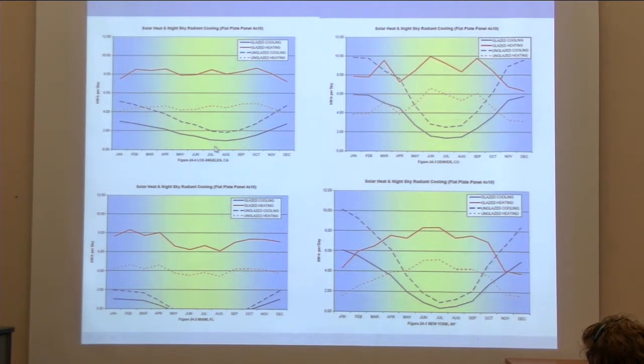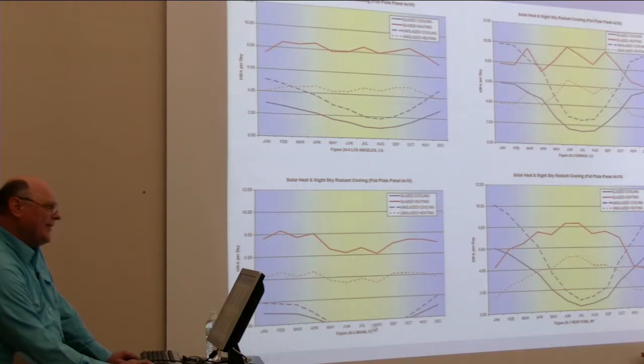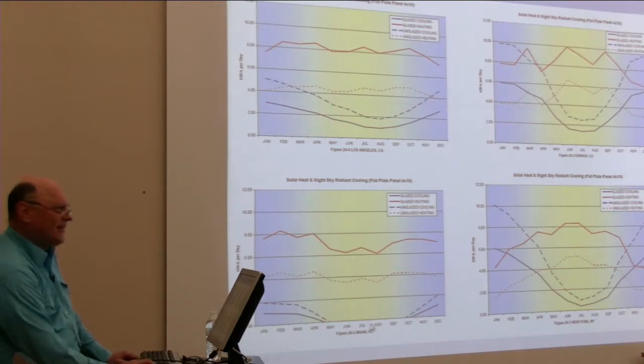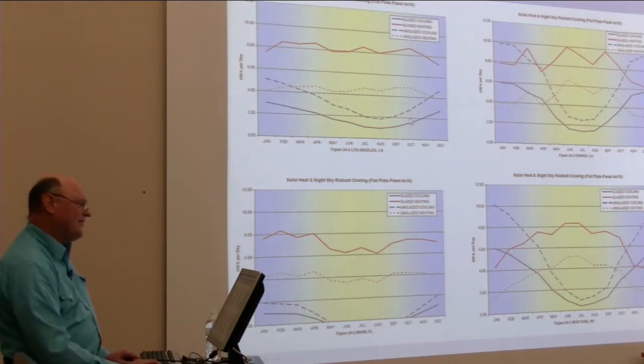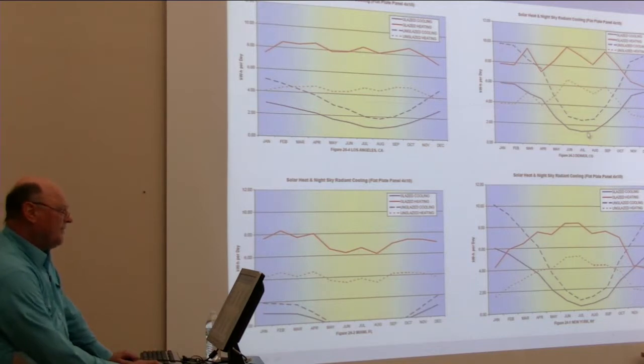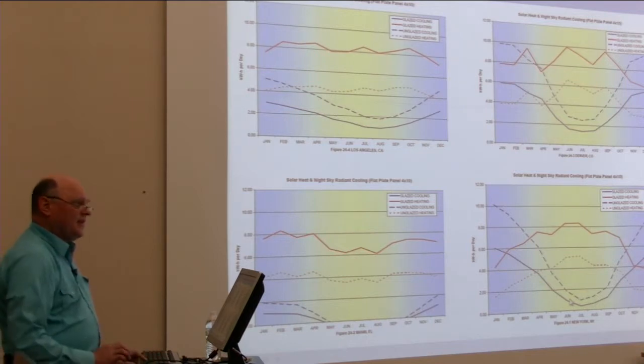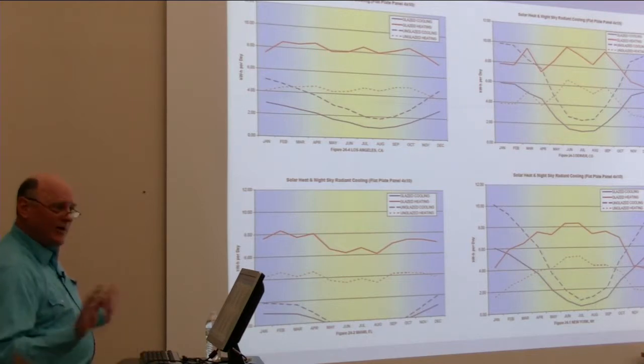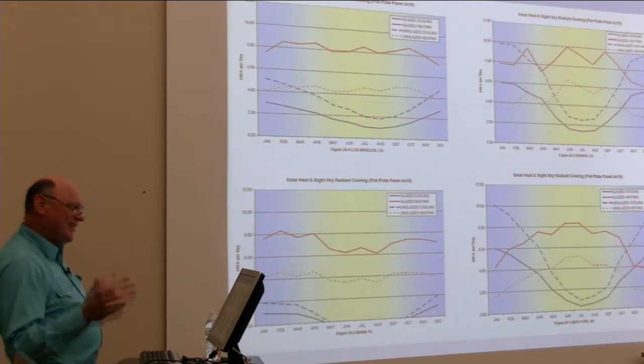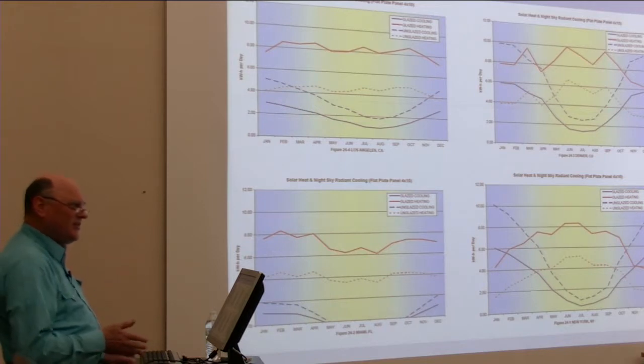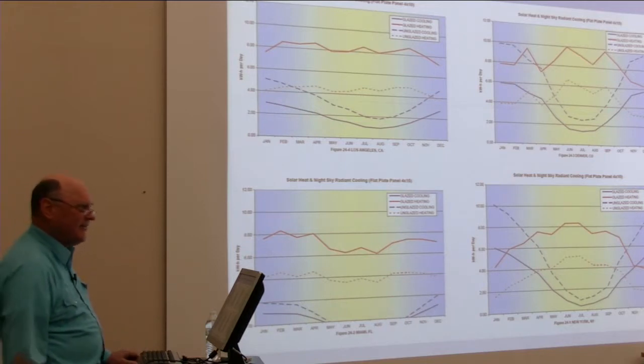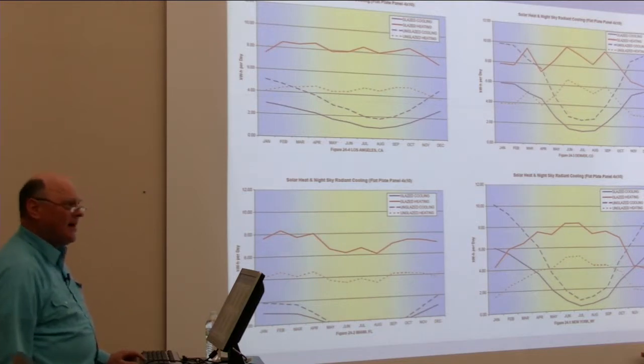Can I get any cooling in Miami where it's really hot and humid? No, it's down to 0 in Miami. So radiant cooling isn't going to work in Miami, but it will work in Los Angeles, it will work in Denver, and it will work, oddly enough, in New York City. It doesn't go to 0 in New York. So radiant night sky cooling, nobody knows about it, but it's just waiting to be used to offset your air conditioner load. Simply by running a pump at night, you can get cooling.